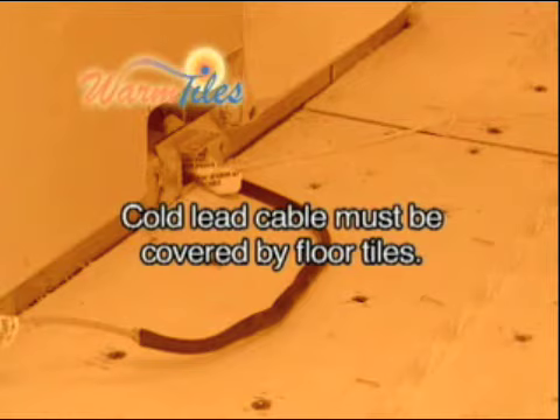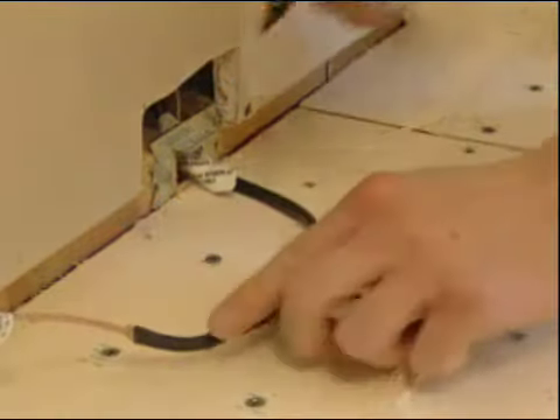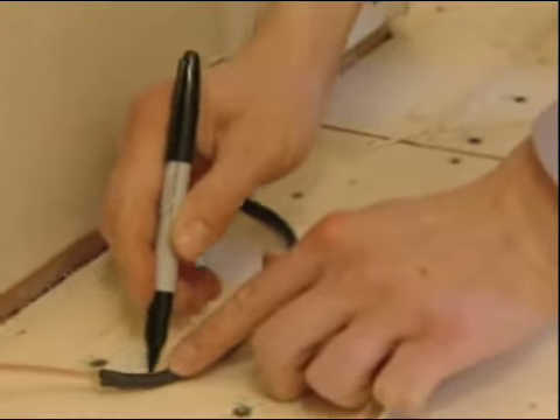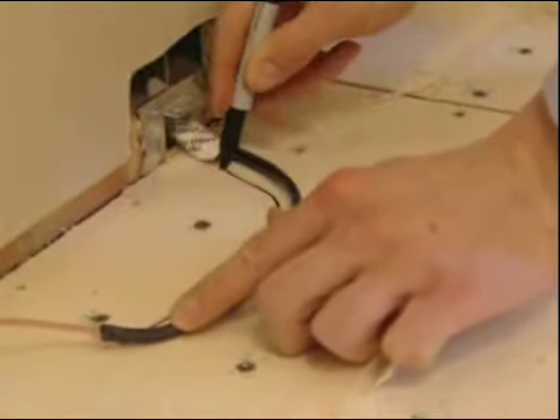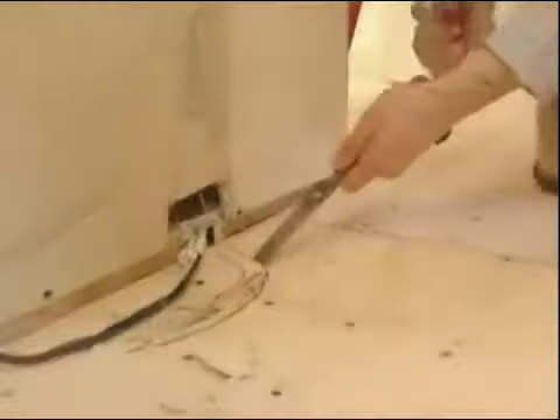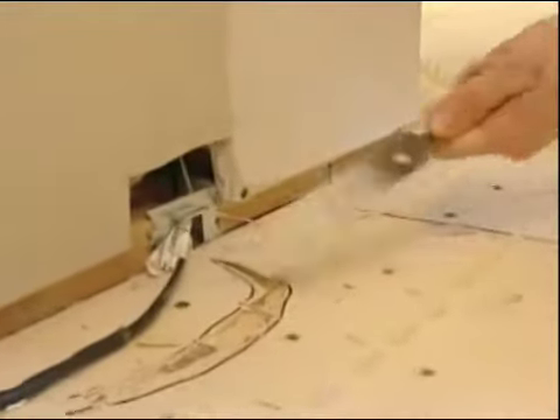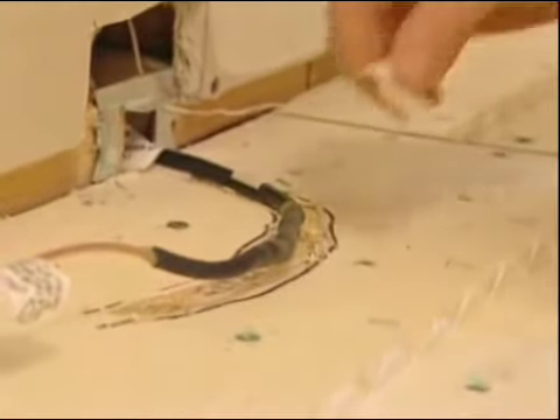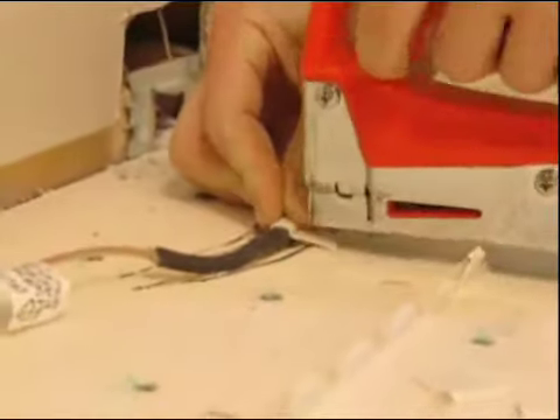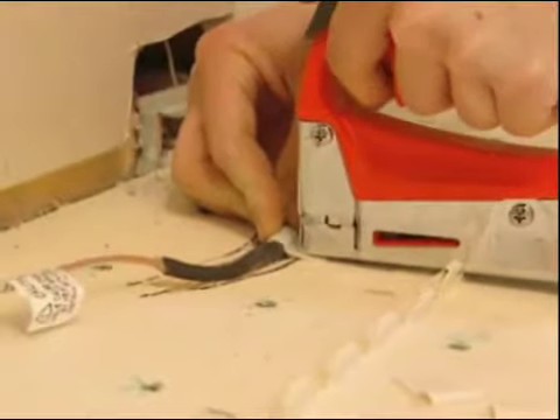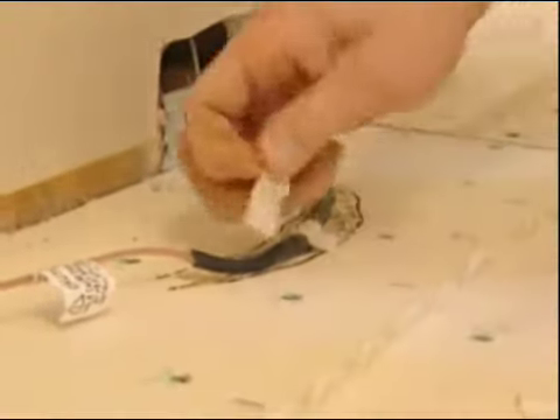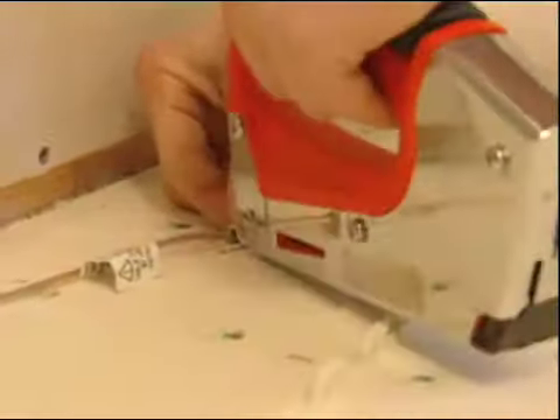Position the cold lead heating cable splice so that it will be completely covered by mortar or floor tiles. Recess the cold lead heating cable splice to the same height as the copper heating cable. The plywood may need to be carved to a depth of 1/4 inch. The cold lead heating cable splice is fastened to the floor using the clips included with the warm tiles cable kit.